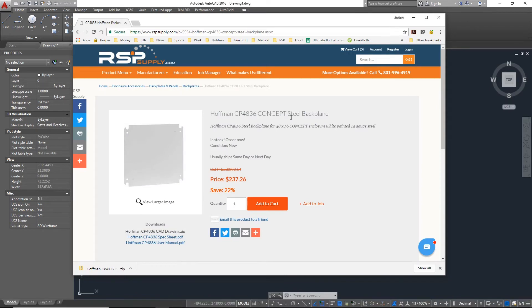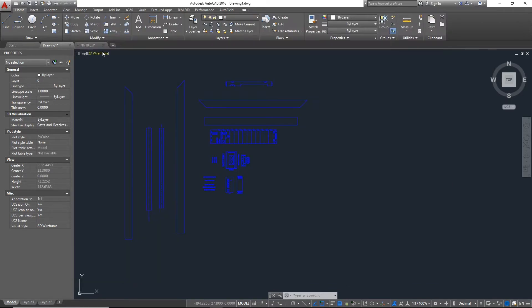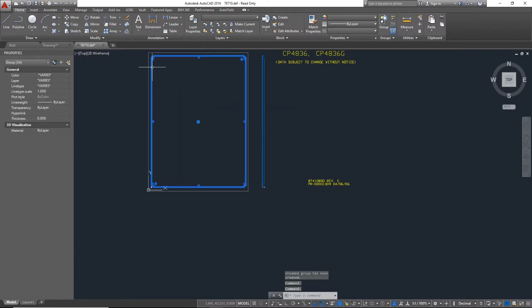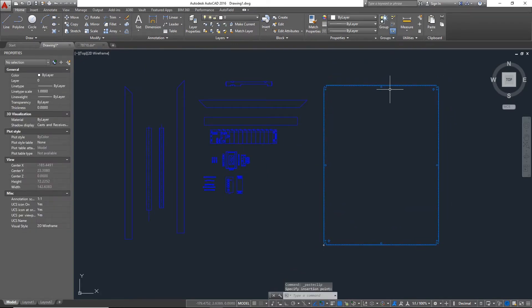Here you can see the backplane that's actually needed for this control panel. If I go to RSPSupply.com, I have the ability to download it right from their site to my computer and import that drawing into AutoCAD, so I don't actually have to manually draw that piece of hardware — I can simply import it. You can see here I'm copying and pasting that right into my drawing so I can better complete the layout process without having to draw these more complex pieces of hardware.